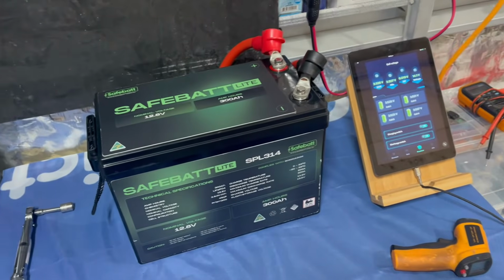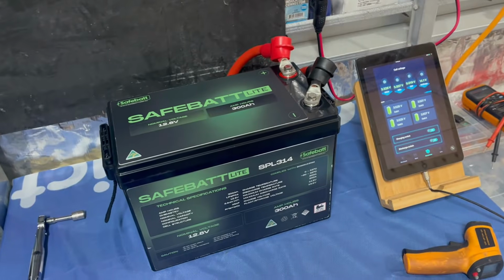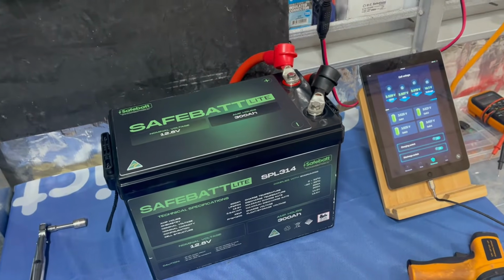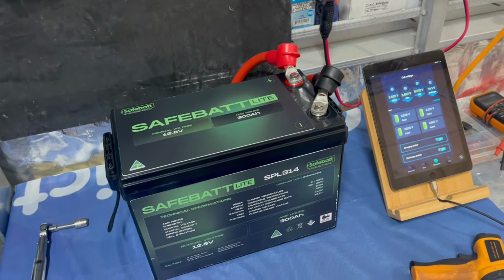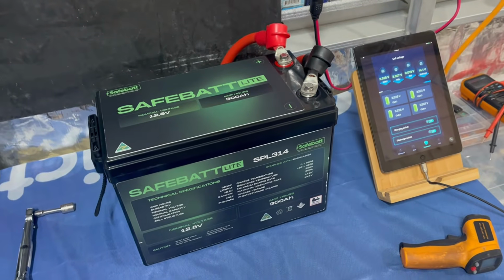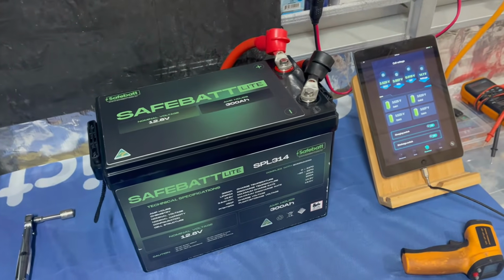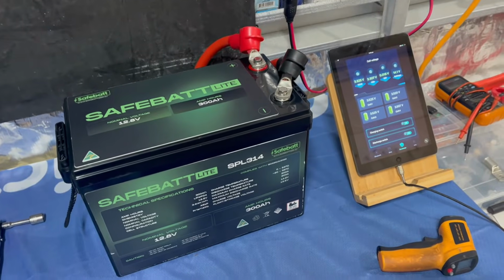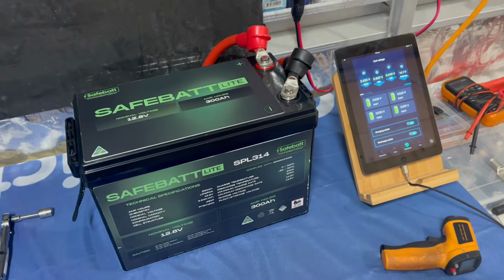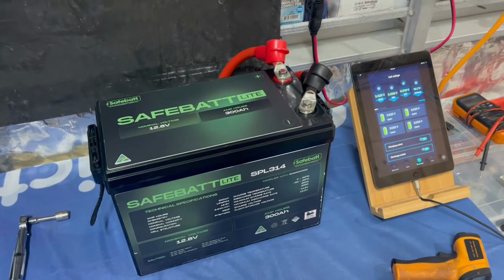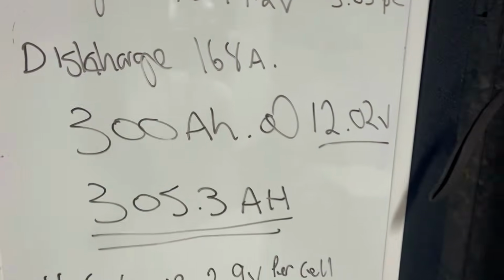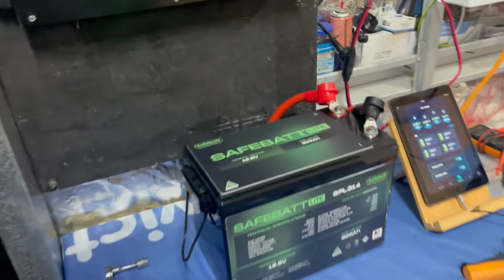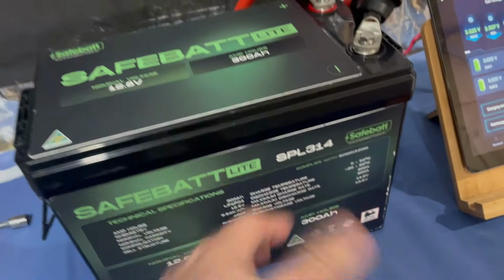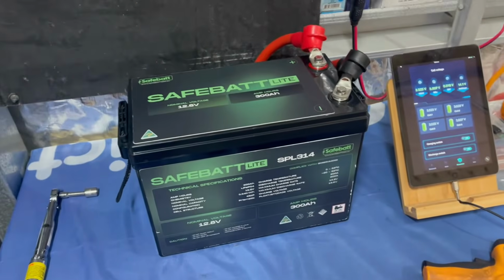So really, really happy so far. I guess the next thing to do is probably another discharge test at a lesser discharge than 170 amps — I'll drop it down to say 100 amps, which might be a little more realistic for a real world test. I say it all the time, nobody's going to cycle these batteries continuously at a discharge rate of 168 amps until the battery drops dead. It's just not going to be a reality. But I do it because the specs say it can be done, so that's the reason I hit them with a pretty hard discharge current.